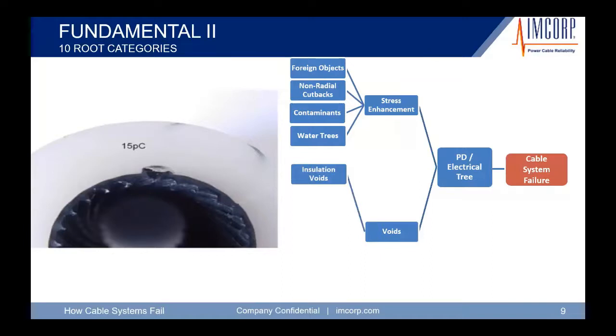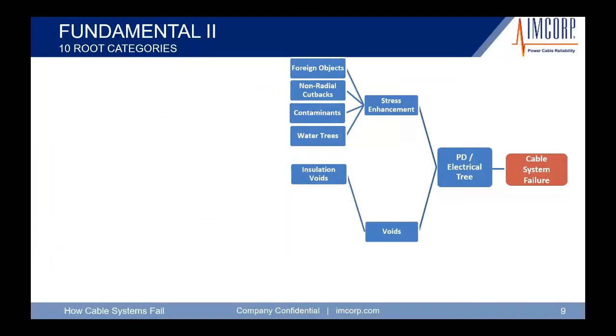Here's a manufacturer's defect that we found. This cable was not allowed to cure properly or long enough, so it had a little issue or a void at the strand shield. Now, over time, this would cause a carbon tree to develop, potentially a water tree as well, making a path to the strand shield and the outside diameter of the outer conductor, making this thing go to failure. We were able to catch this prior to energizing the cable. Did it on a commission test.